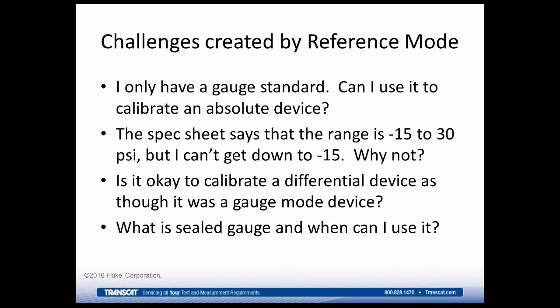Now, there are some challenges created by these different topics, specifically reference mode, and we'll look at each of these questions individually. If you only have a gauge standard, how do you calibrate an absolute device? Or you see things like negative 15 to 30 psi, but I can't get down to negative 15. We'll talk about some of the challenges with differential devices and also some of the unique terms like sealed gauge. What does that mean, and how is that different from gauge mode?